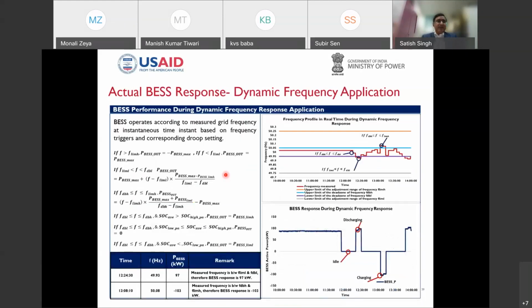Now this is interesting application, dynamic frequency application, where the intent is to modulate the output from the batteries so as to respond to the real-time frequency variations. And these are basically the control logics which have been fed into the controller. However, if you say that my initial frequency bands were 49.95 and then 50.05, and this is the actual frequency in the red kind of graph. And whenever this is within the band, the battery should ideally respond, and the output should be 0.